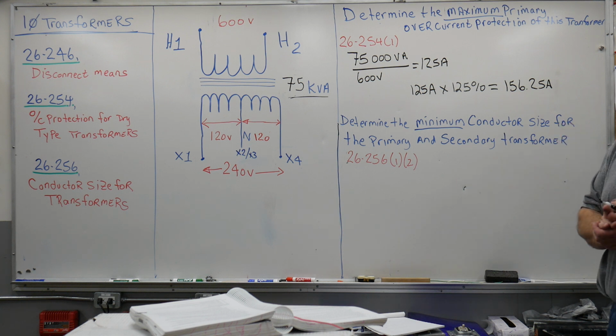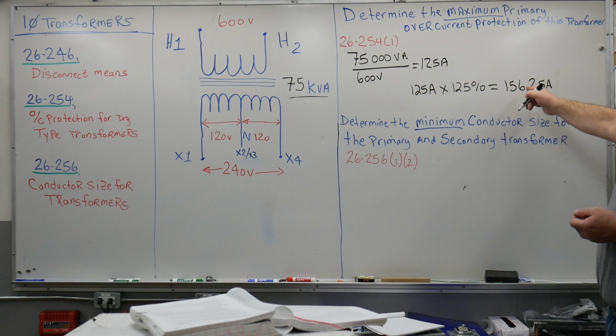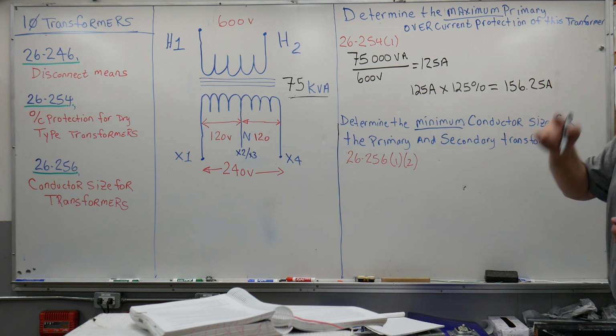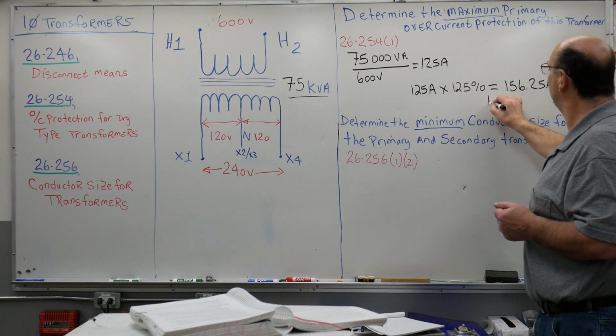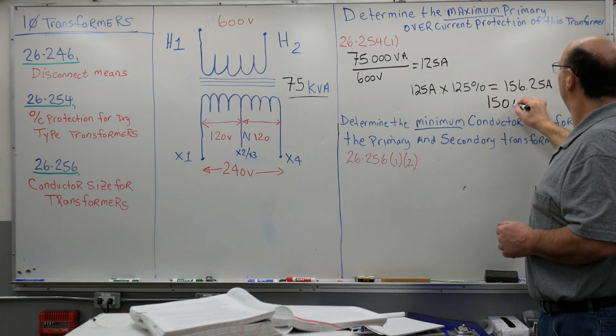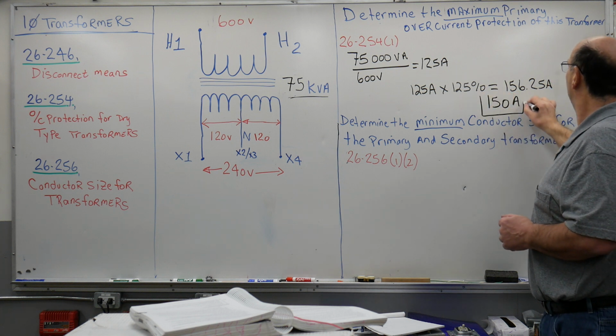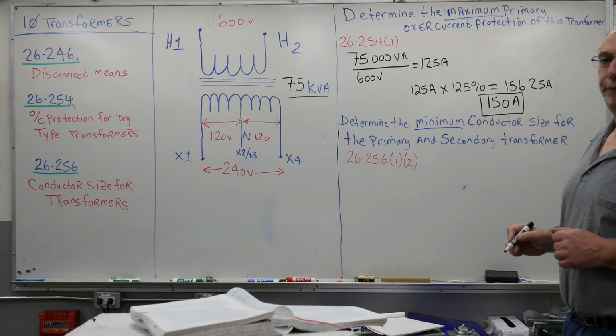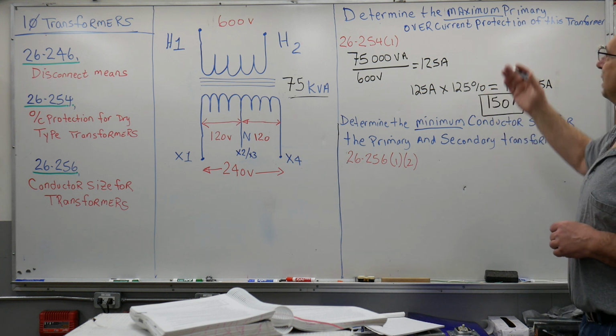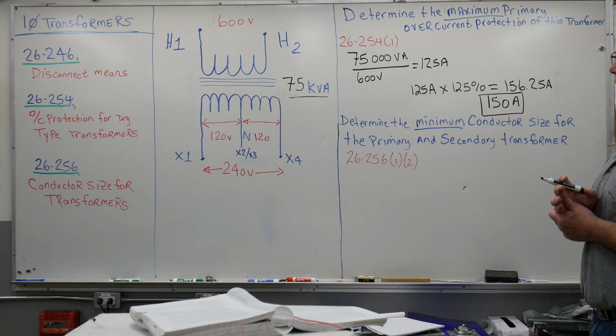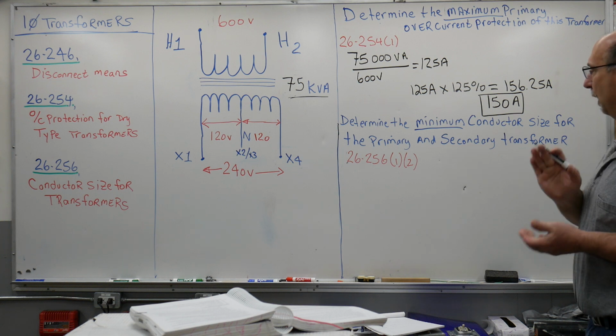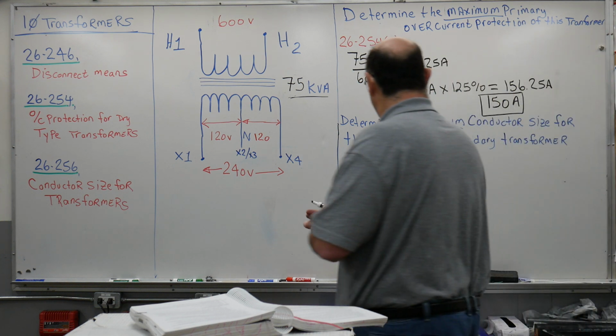Now, they do not make a 156.25 amp overcurrent device, so considering that's the maximum, then we have to go down. So we have to go down to 150 amps, which is our maximum overcurrent device for this transformer. All right, just that easy.